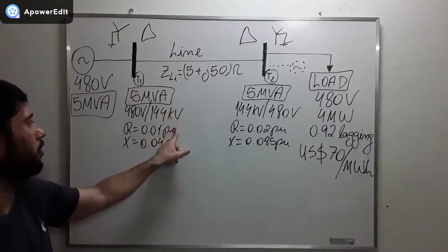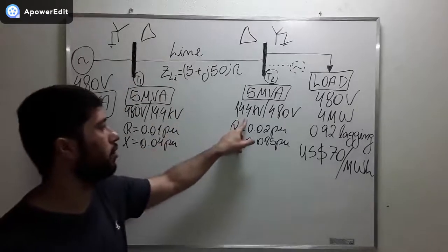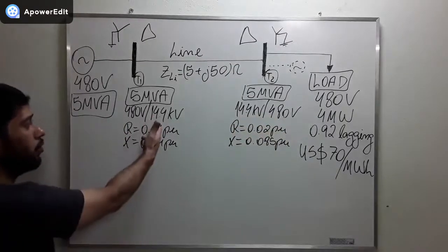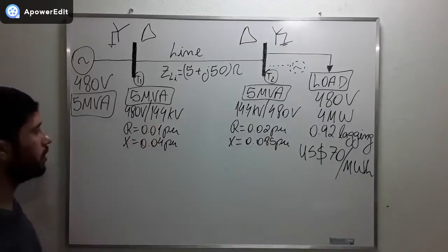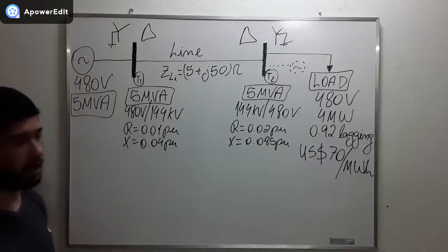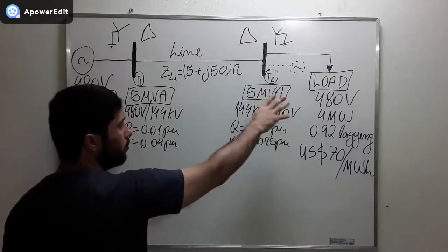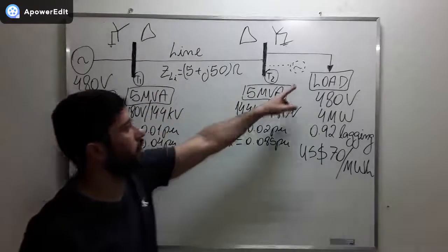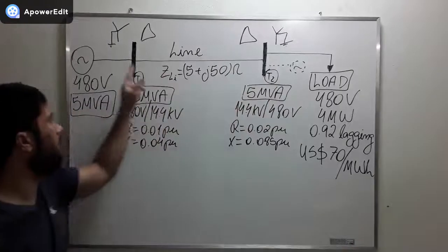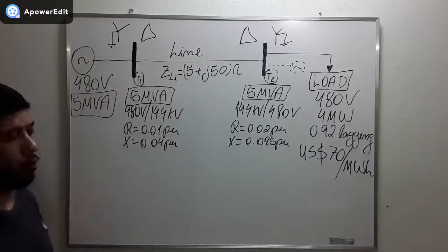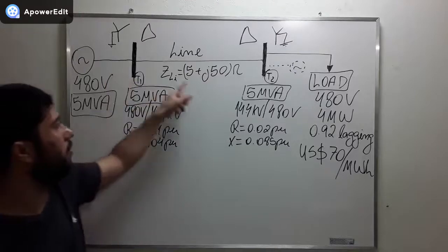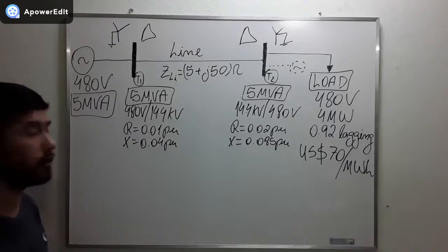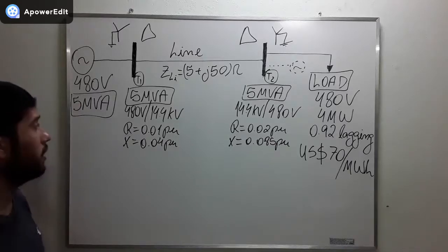480 to 14.4 kilovolts and 14.4 kilovolts to 480. And when you increase the voltage, what do we do with the current? We decrease the current. So the same current is going to flow through the system? No, it will not. This current here is not the same as this current here, and is not the same as this current here. How do we calculate then if the currents are different? We need to normalize the current somehow, and this is exactly what the per unit system of measurements does.